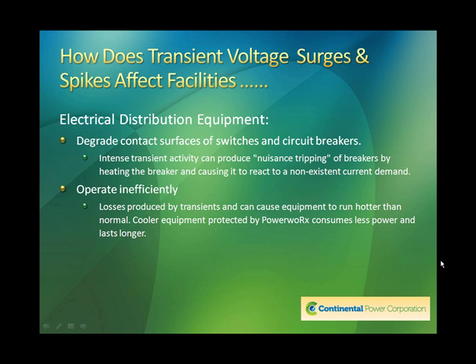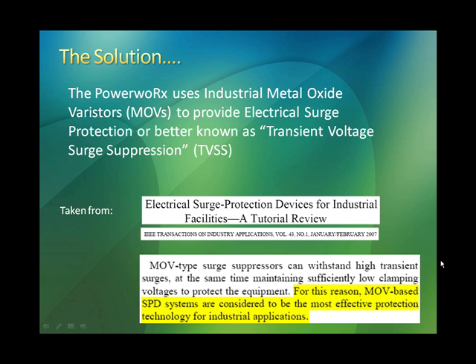The solution is the PowerWorx, and the PowerWorx has built within it industrial metal oxide varistors, or MOVs for short, to provide electrical surge protection, better known as transient voltage surge suppression, or the acronym TVSS. I've got an article shown on the screen there from the IEEE Transactions on Industrial Applications, Volume 43, Number 1, from back in 2007, titled Electrical Surge Protection Devices for Industrial Facilities, a tutorial review.